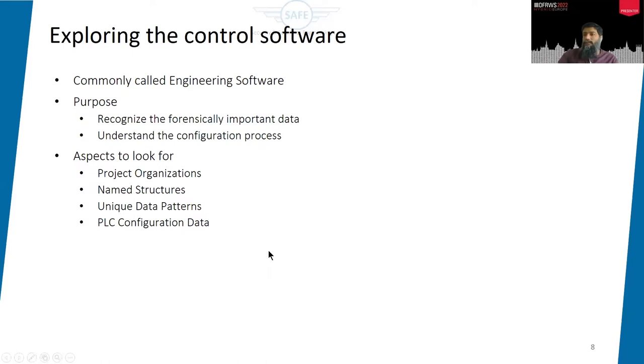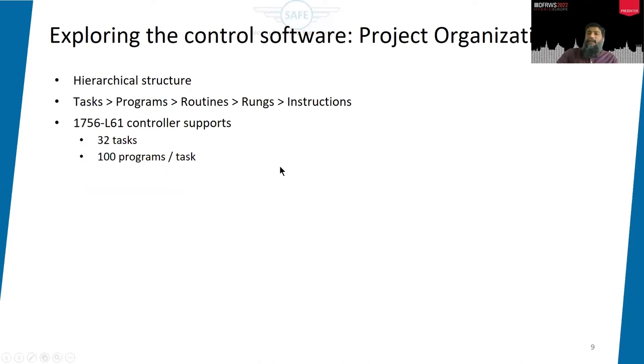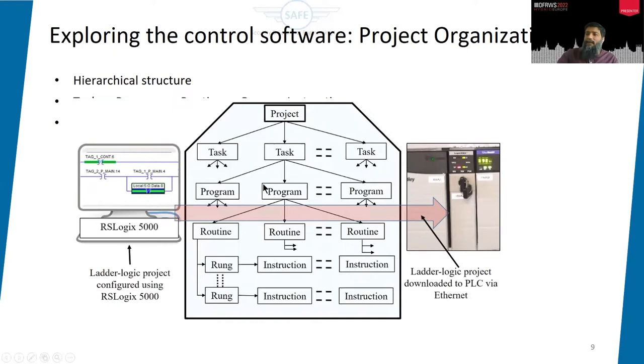In Allen Bradley, the project is organized in the form of tasks — there are up to 32 tasks in one project. Each task has up to 100 programs, each program has multiple routines, each routine has rungs, and each rung has instructions — a five-layer hierarchy. We can name the routines, programs, and tasks. We create a program in RSLogix 5000, the engineering software or control software for this particular PLC, and push it to the PLC.